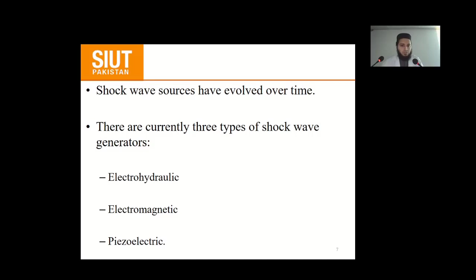Application of a high voltage electrical current between two electrodes about 1 millimeter apart under water causes discharge of a spark. Water around the tip of the electrode is vaporized by high temperature, resulting in a rapidly expanding gas bubble. The rapid expansion and then rapid collapse of this bubble generates a shock wave that is focused by a metal reflector shaped as a hemi-ellipsoid, as in the original Dornier HM3 lithotripter.